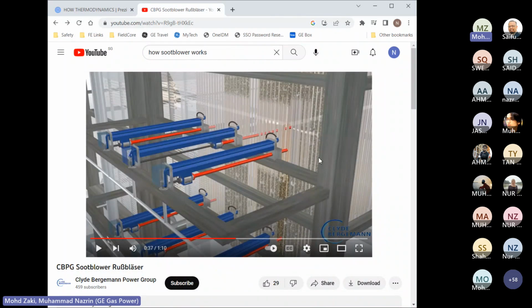Inside the boiler, because of the thinness of the boiler tube, we have to strategize the soot blower operations. We have a certain period of time we need to run the soot blower to clean the boiler tubes. In a combined cycle power plant, we don't have the soot blower because the tube is clean. So only for coal plants, we have this soot blower to clear out the slagging and fouling and to improve the heat transfer and get back the temperature.